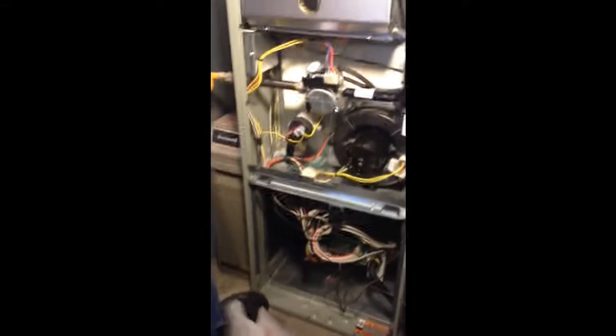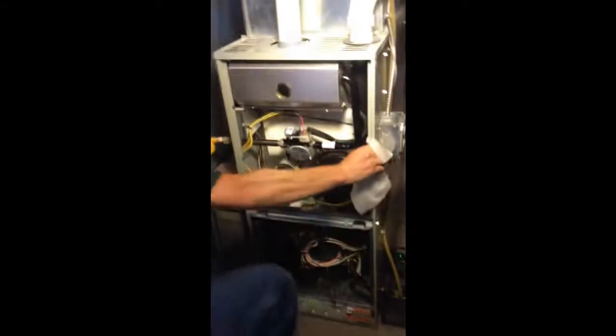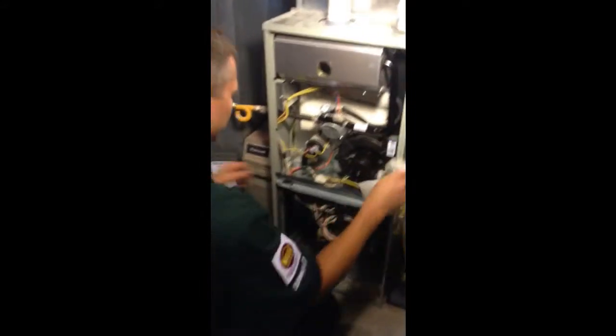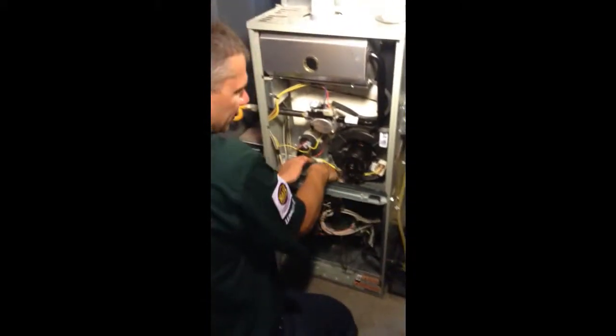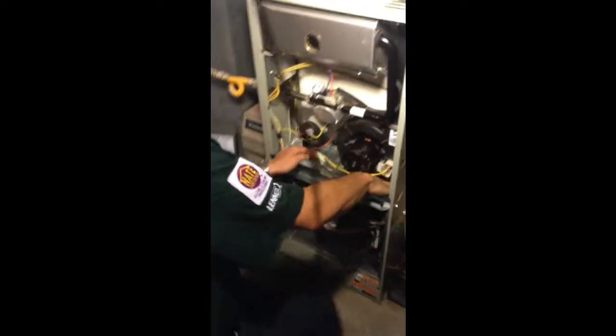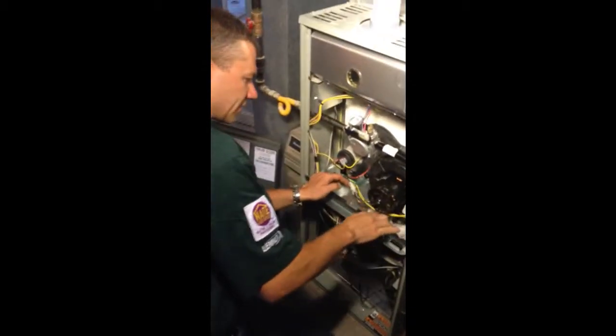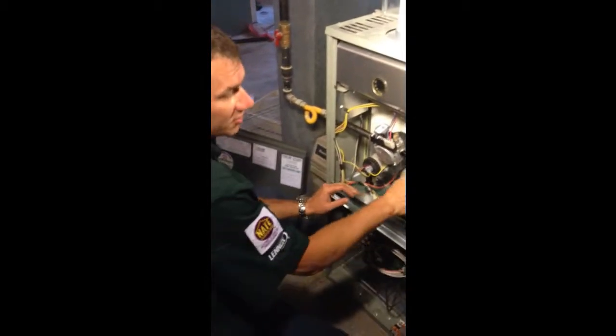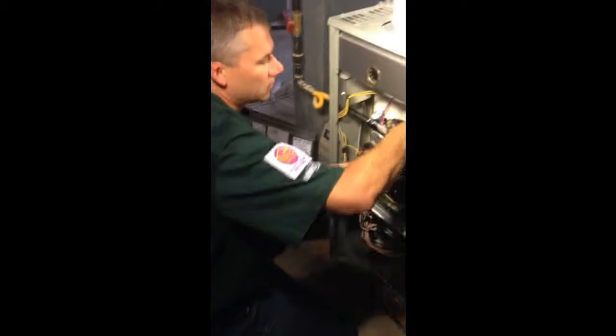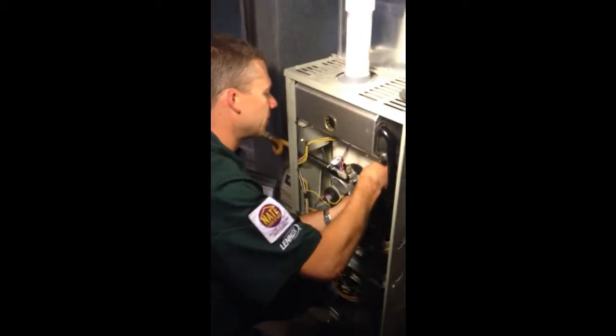That's the best way, or the fastest way, to tell whether there's a hole in the heat exchangers. If the rust breaks through the heat exchangers, or if there's a crack or a hole in it, that'll go up over 100 parts per million, the carbon monoxide. Right. And at 55 parts per million, you could start getting headaches. Wow. And then I guess federal law says that you can't have it over 400 parts per million, but Washington state law says only 100 parts per million.